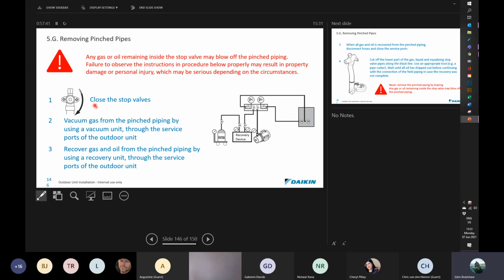Okay, it's very important also to take note. Make sure that the stop valves are closed. Okay, vacuum any gas from the pinched piping by using a vacuum unit through the service ports on the outdoor unit. Or you can recover the gas and oil from the pinched piping. I think most times the guys will just clean it out, make sure there's no excessive gas. Make sure that the valves have not leaked as well.